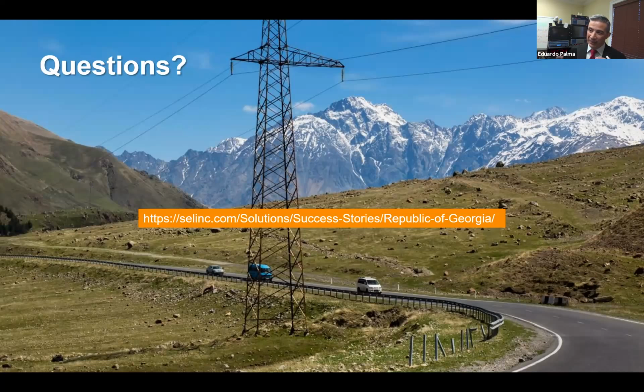When those milliseconds start to shrink, then we're in trouble because we have to compensate in other ways. And what happens when you physically connect, in a distributed way throughout your country, distributed energy resources that might be inverter based, like the solar plants and the wind plants? They have an inverter, and an inverter changes DC to AC in a step change, meaning that it's extremely fast.